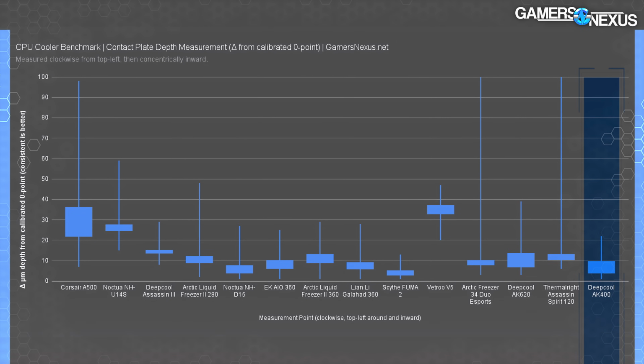Our surface flatness testing is next. This uses even more specialized testing equipment in our test lab, and it tests the actual consistency of the cold plate surface as it mates with the IHS. This bonds well with the pressure testing we do to form a full picture of the contact quality.